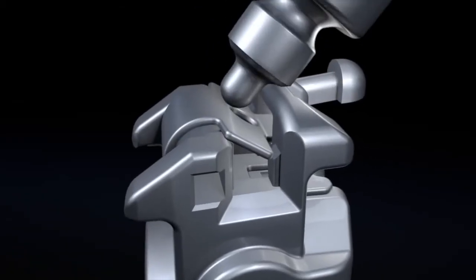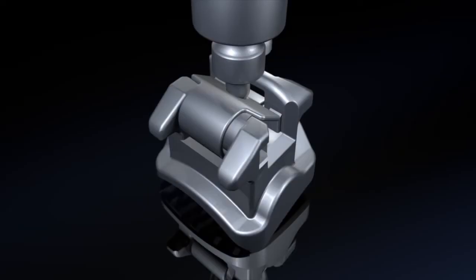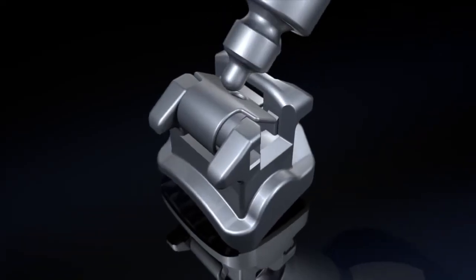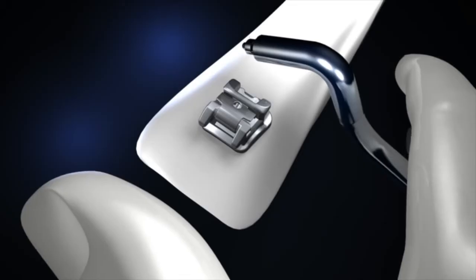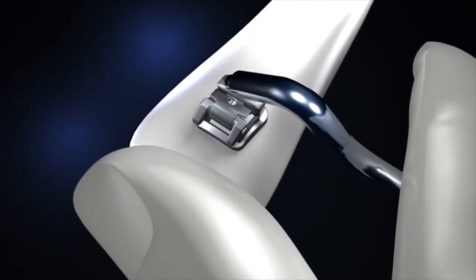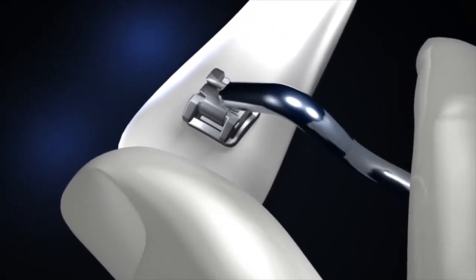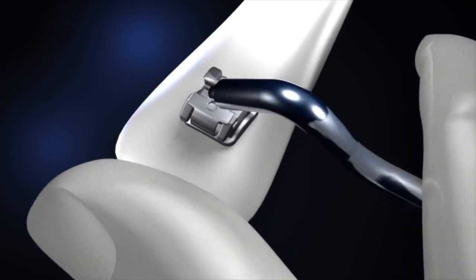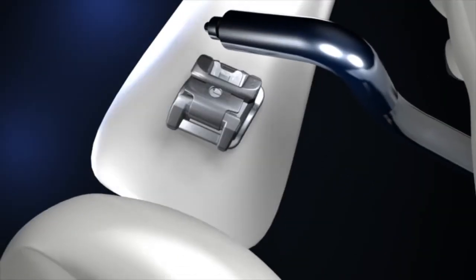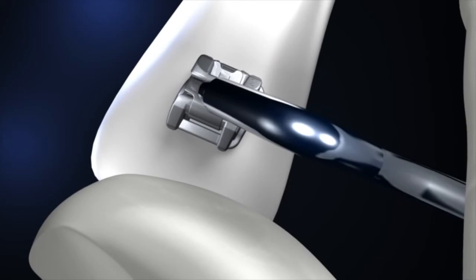The tip of the new BioQuick probe is specially designed to prevent involuntary leverage from causing damage. A useful trick is to hold the probe horizontally with four fingers of one hand and rest your thumb on the tip of the tooth. This makes it impossible to accidentally use the probe as a lever.